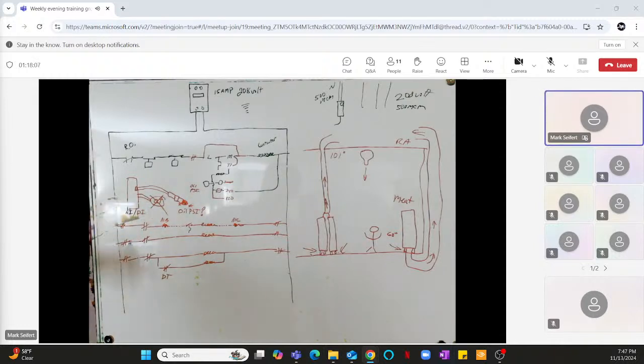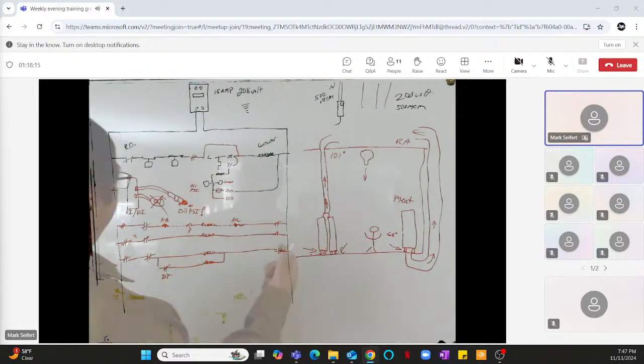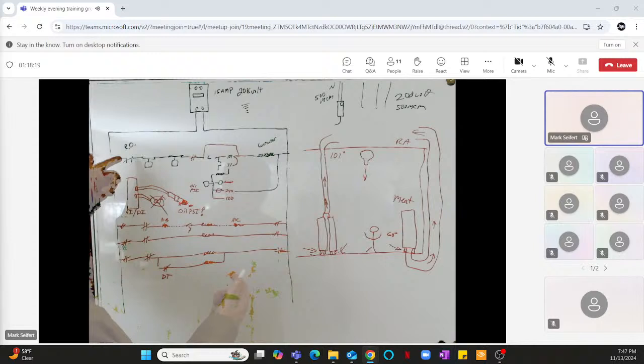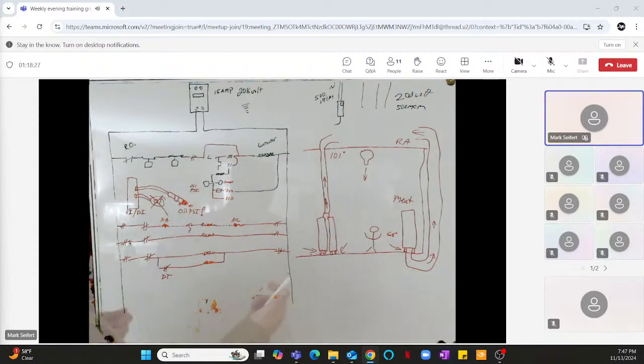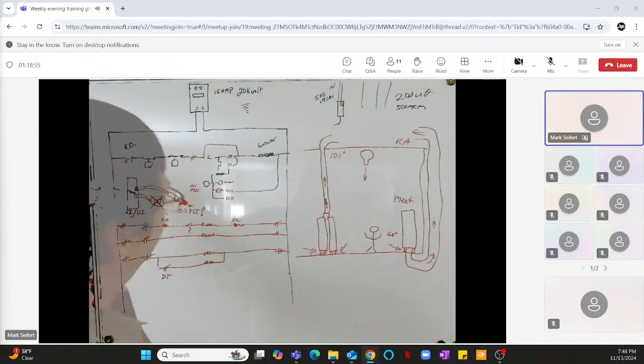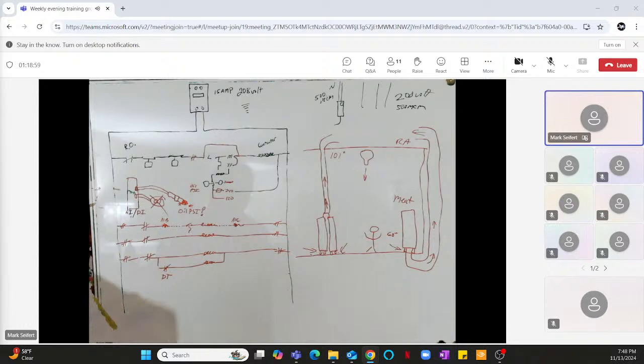The CT is a closure. It's an on-off switch. Basically, it'd be the same thing if you had a guy standing there with a gauge and it came on. Compressor, it called for it to come on. It shows a light. It called for it to come on. And the guy is standing there looking with an amp probe and an oil pressure gauge. And the minute he sees the amp probe go up, he flips a little switch. All right, sends that information. And then the oil pressure gauge goes up, flips the switch. All right, now it's got oil pressure. It's just giving the information to the computer to make its decisions on whatever it's been told to do. So it's a more high-tech way to do it. I mean, that's fine. It works fine. I honestly have very little good things to say about how Danfoss does it, but it works as well.